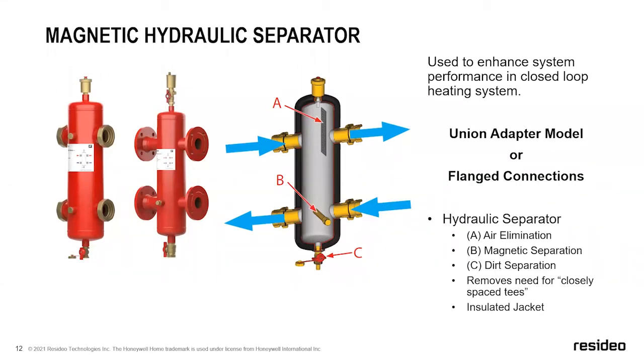So first off, it's going to be your air elimination. So when you use our product, you no longer need the Spirovent. This is going to take care of your air elimination. And I'll talk a little bit more on how that works. It's also going to do your dirt separation. So if you've got flux in the system, if you've got a little bit of Teflon tape, whatever's left in the system from the assembly, it's going to basically drop it down and collect it in the bottom of this. The other thing this is going to do is it will also do magnetic separation.